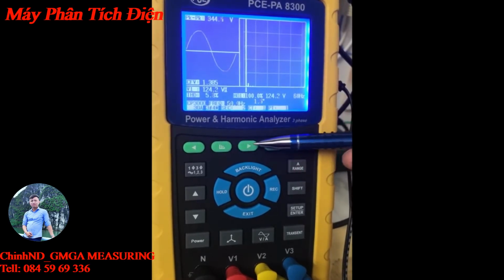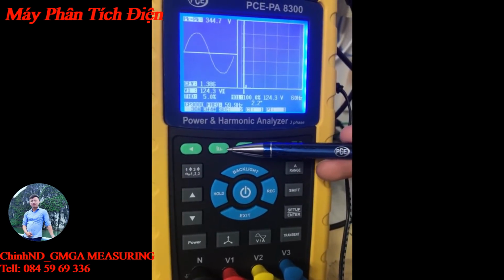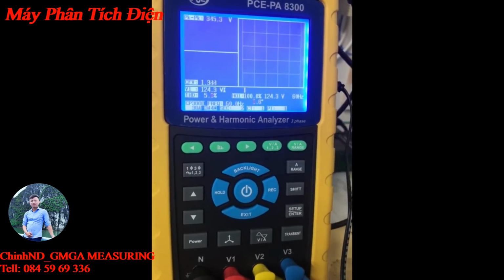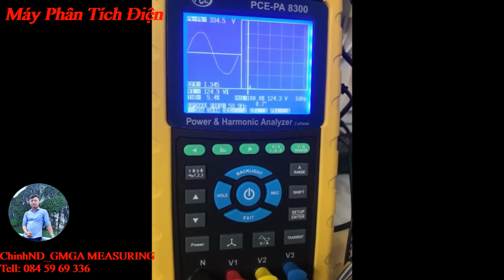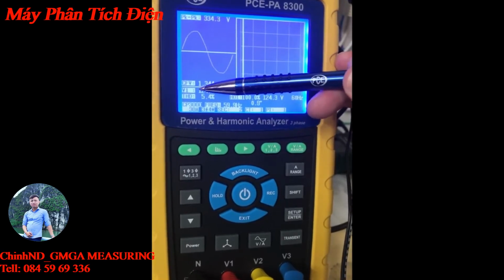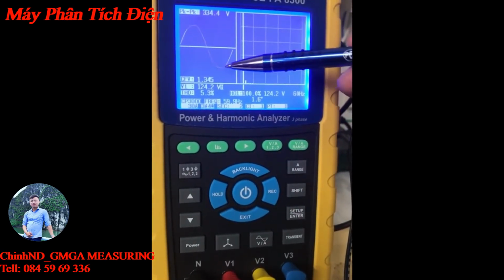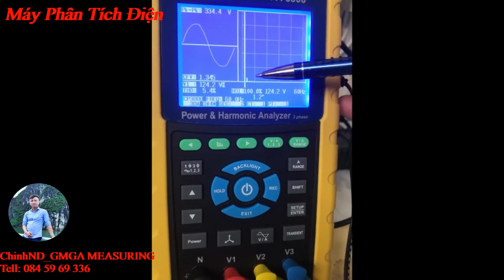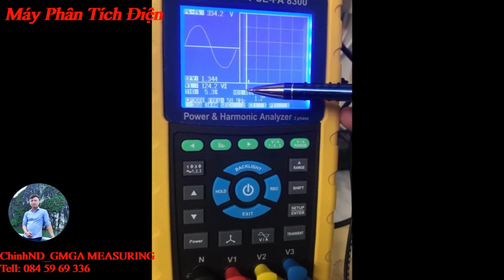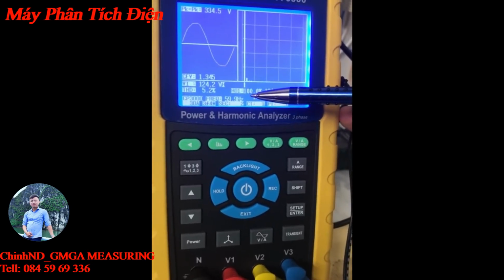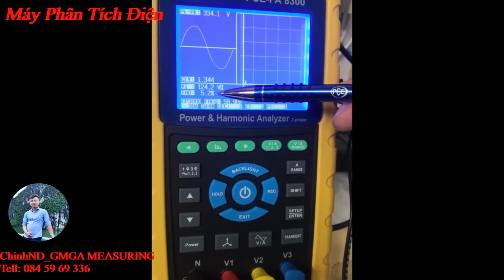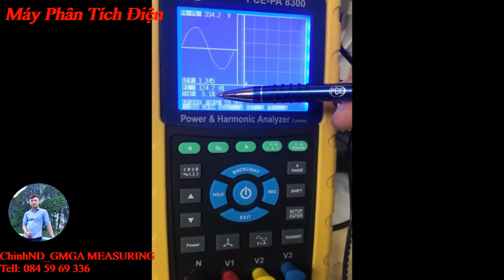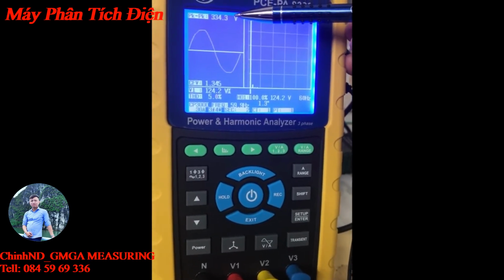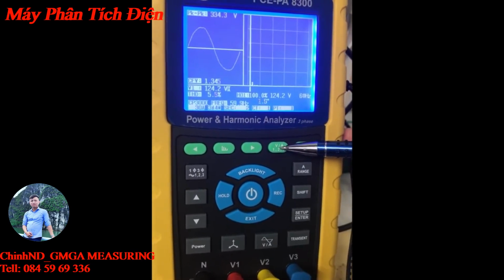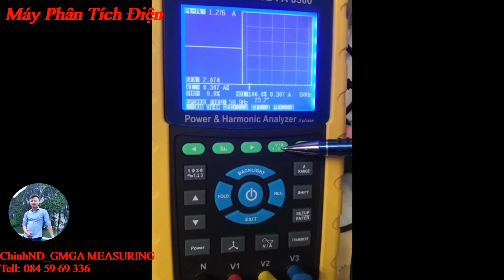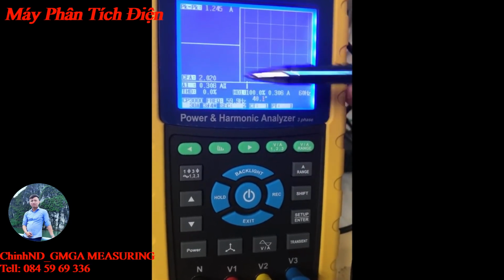These green buttons here are going to be your harmonics analyzer buttons. If you select this button, it's going to give you a split screen telling you this is your phase 1 voltage, displayed right here. This is going to be your harmonics analyzation 1 through 50. So you can see this is harmonics 1, giving you a total harmonic distortion value of 5%. It's also going to display your peak to peak voltages. Then you can also scroll through and select different phases as shown, your current.